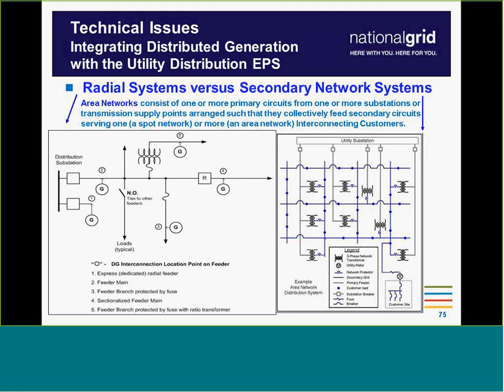With networks, you've essentially done that twice and interconnected everything. When we designed that system, we never planned for DG because we didn't expect people would want to connect DG on a network. The issue is we have equipment called network protectors, which are only designed for power flow in one direction. When a distributed generator connects to that system, it creates potential for backfeed through a network protector.